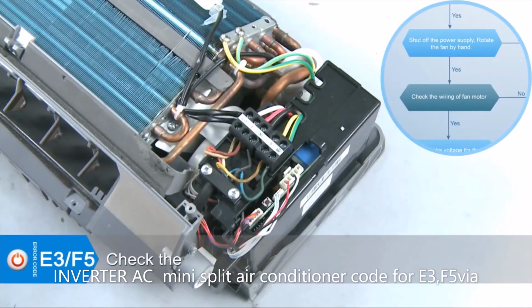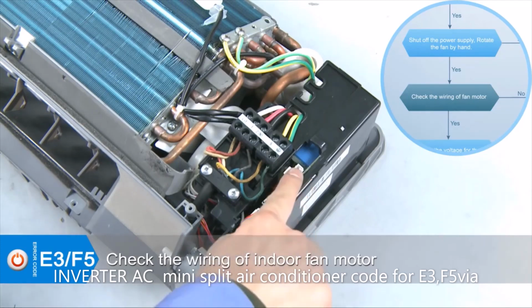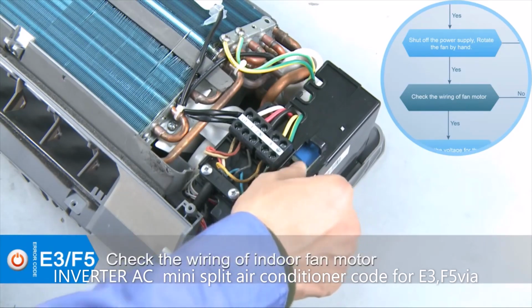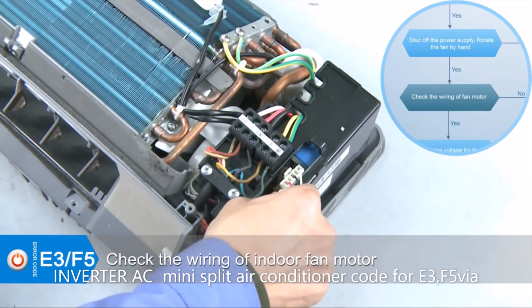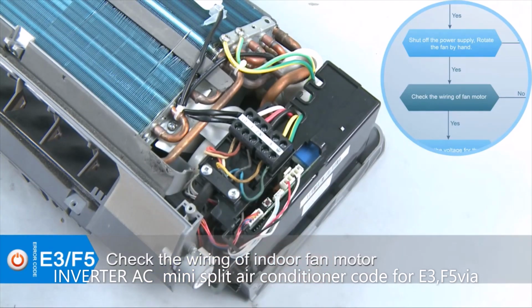Examination for the indoor fan motor. Taking AC motor with feedback as an example, it has 2 pins. Separately, 3 cores pin connects to the power supply. 5 cores pin is used for signal transmission. If the connection is correct, check the fan motor.